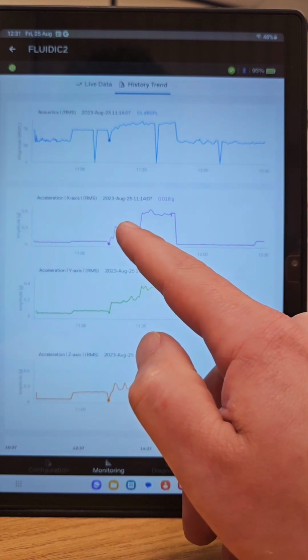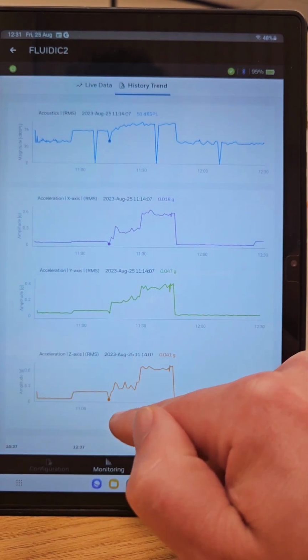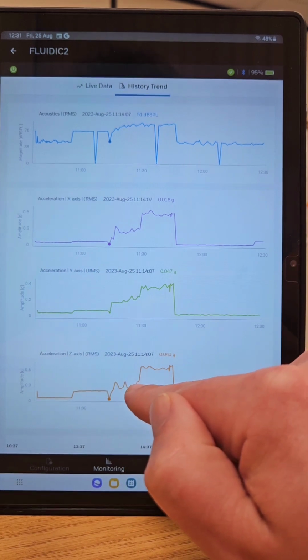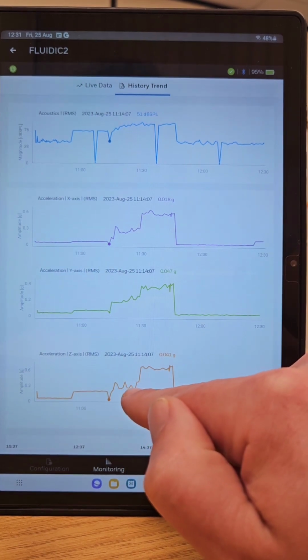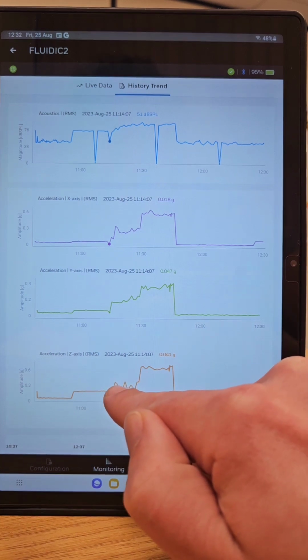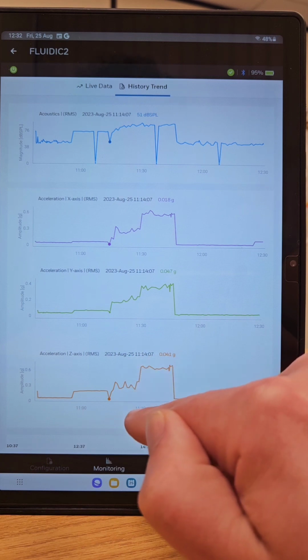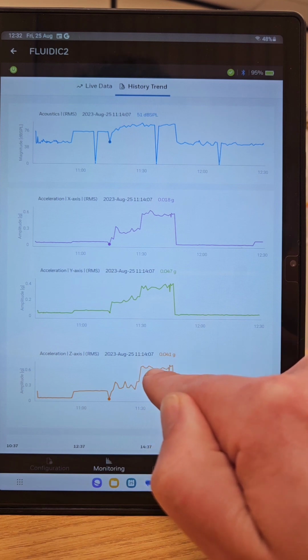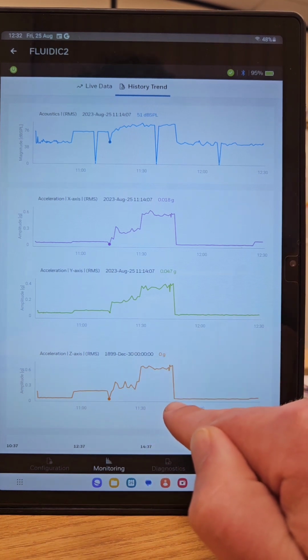And I can certainly see the acceleration, the vibration is picking up. This one's very clear on the z-axis, because at 11:30, 29 minutes past, this timestamp, I went from number one setting to number three on the fan, which shot this up on that graph anyway. It's quite clear, imbalance number three, then I've switched the fan off again here at the end of the video, which was 11:45.